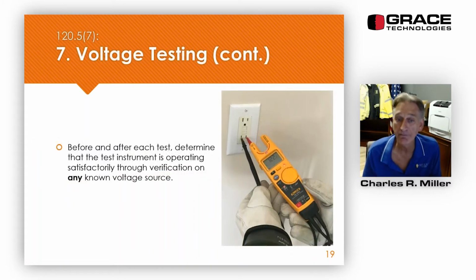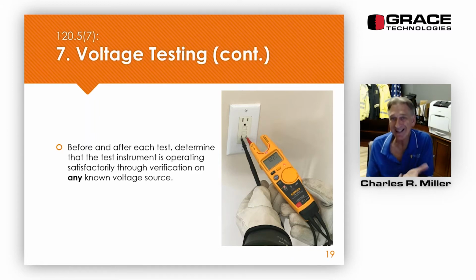All right, before and after the test, we have to make sure that the test instrument, typically electricians, we typically call it voltage detectors, but the technically correct name is test instrument. Before the test, we have to make sure the test instrument is working properly by using it or verifying it on any known voltage source.